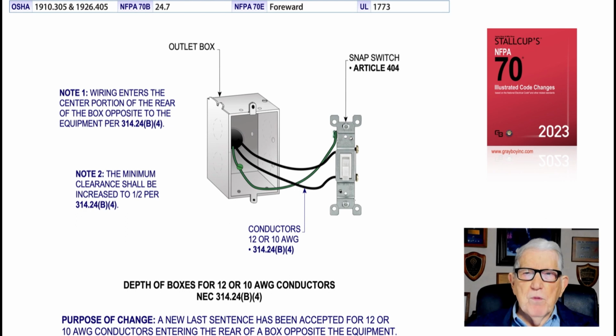Wiring enters the center portion of the rear of the box opposite to the equipment in accordance with 314.24(B)(4). And then note 2 expands on the rule and says the minimum clearance should be increased to a ½ inch per section 314.24(B)(4). And so what they're basically saying is you need this extra ½ inch room to protect conductors and have airspace that would be appropriate for the circulating of heat that might develop, so to speak. And that's what this illustration is illustrating to the user of the NEC.